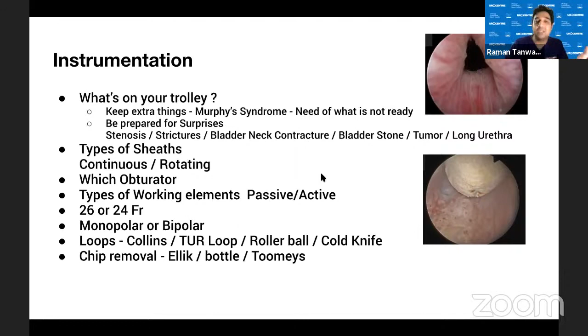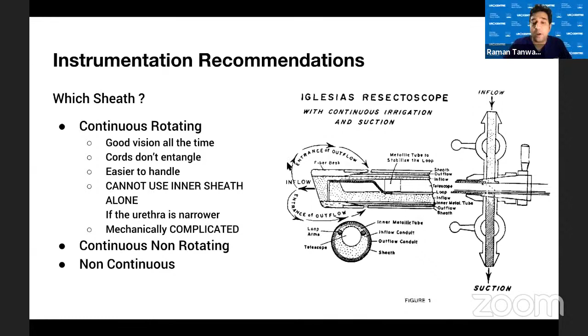So as Dr. Rishi has told, we are now using the continuous rotating sheath. One small thing that I wanted to add to what Rishi sir said is that the continuous rotating sheath has a single inner sheath. So there is no inlet or outlet in that sheath. So if you have a narrow urethra, then you cannot put that 26 French assembly inside. If you had the inner sheath which was a continuous non-rotating one, then you would have an inflow and oblique outflow channel in that sheath. So there's one disadvantage of this continuous rotating sheath, which is that you cannot use this inner sheath independently, whereas in the other models, you could use the inner sheath independently. This is a very important point from the practical aspect also.